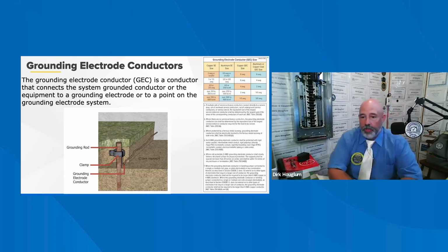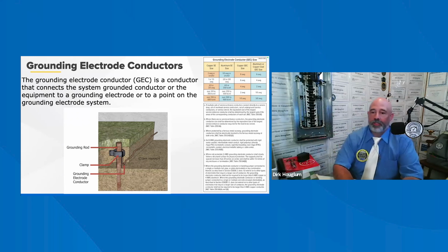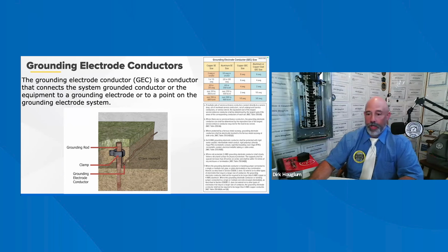Now, the equipment grounding conductors, the grounding wires, are also brought to this point and tied to the grounded service conductor, the neutral conductor, and the grounding electrodes. And we are just going to keep moving on.